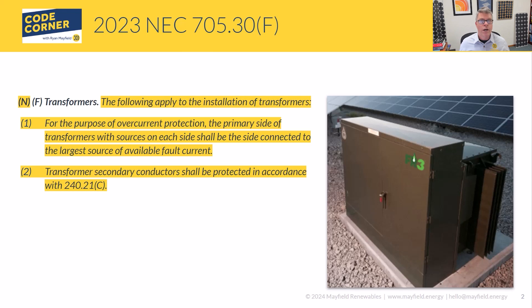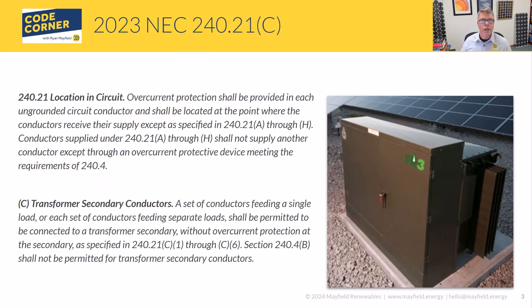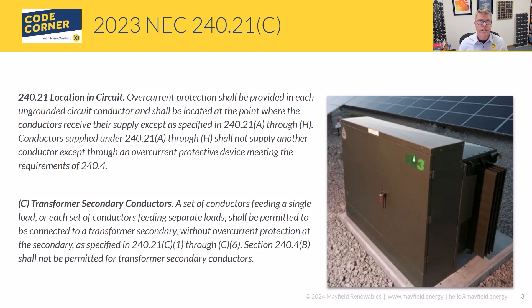Once we have that established, transformer secondary conductors are going to be protected per 240.21C. That establishes how we protect the secondary side of our transformers. Article 240 is overcurrent protection — protecting conductors and equipment. When you look at 240.21, it talks about the need to protect both conductors and transformers, and there are requirements for both. We can use the same overcurrent devices to meet both requirements; we just have to look at both and make sure they're satisfied.